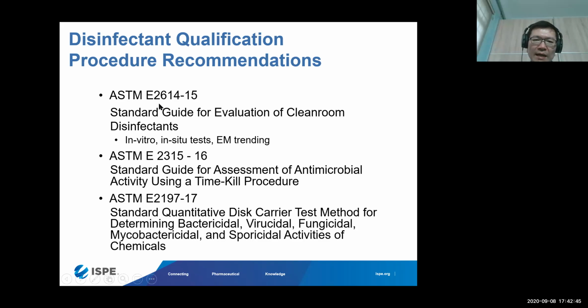If you look at ASTM E2614, this is the standard guide for evaluation of clean room disinfectants. In this guide, they mention in quite some detail the in vitro study requirements, the in situ tests, and also the EM trending. They also refer you to the relevant guidance document numbers for performing the efficacy studies. These are very useful documents to look at.